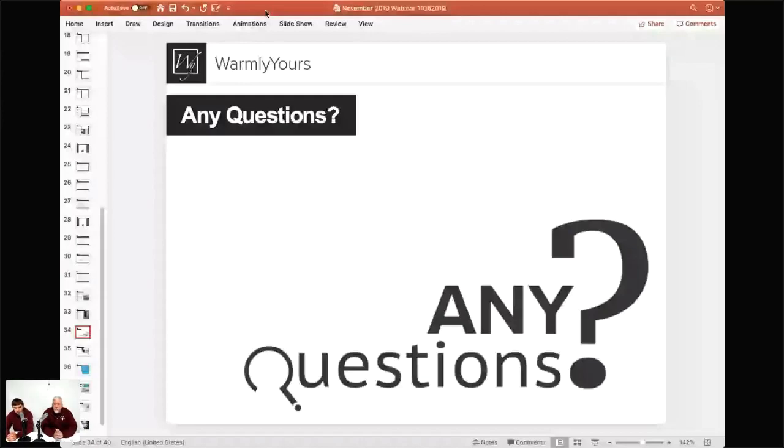Ken has the same question. I used a Mysa thermostat that graduates the tension on need. Will your wires be compatible? Actually, Ken, this morning I was researching that Mysa thermostat. So it looks like a new product on the market that, from what I see, should be fully compatible with the floor heating. We're still in the middle of the research, but it seems to be a line voltage floor heating thermostat that has a floor sensor. So it should operate just as a normal thermostat.